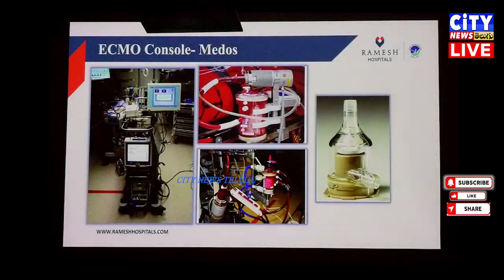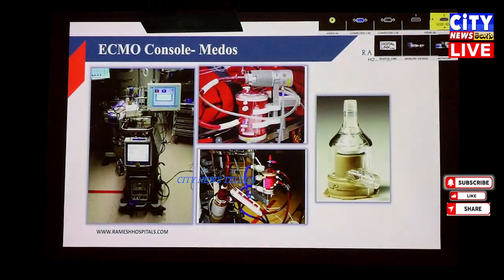This is the system by Medos. This is what we have. Again, this will have a console which will control the pump, a blender and monitoring system. Then this is the pump which will function as the heart, and this is the oxygenator. These pumps are generally centrifugal pumps, so there are impellers inside which rotate through magnetic levitation, and that's how they propel the blood forwards.